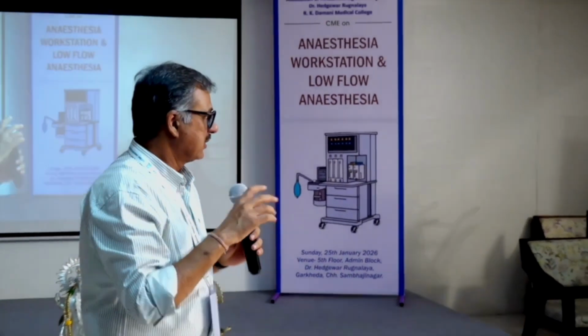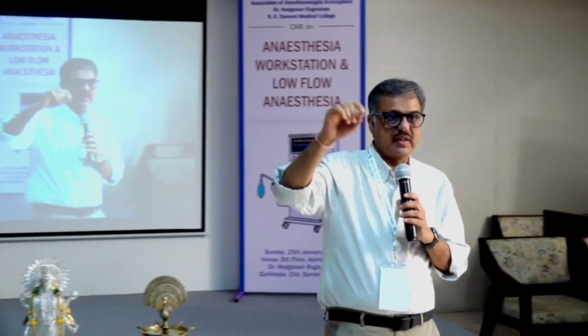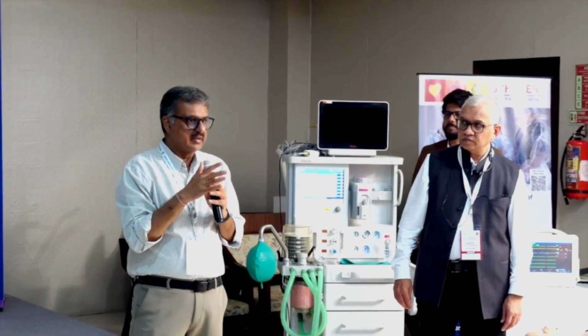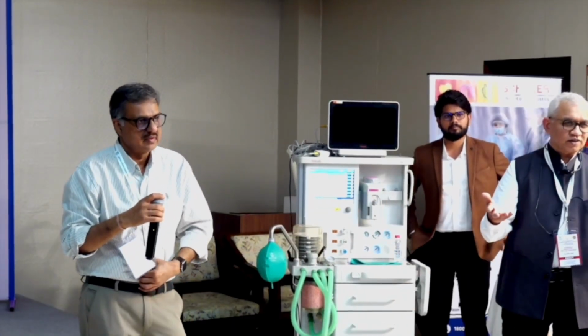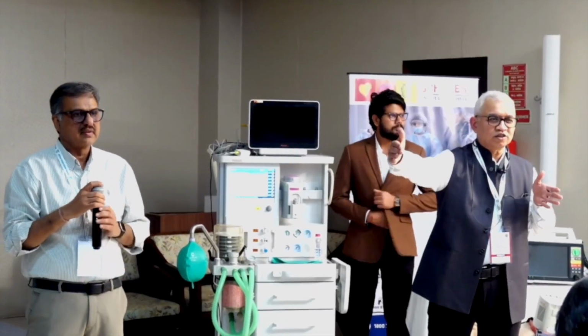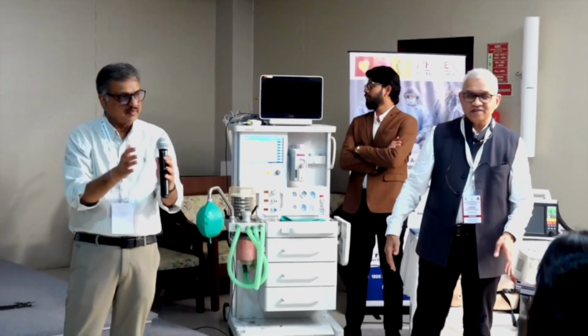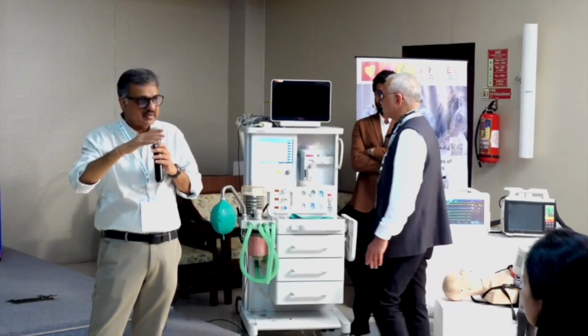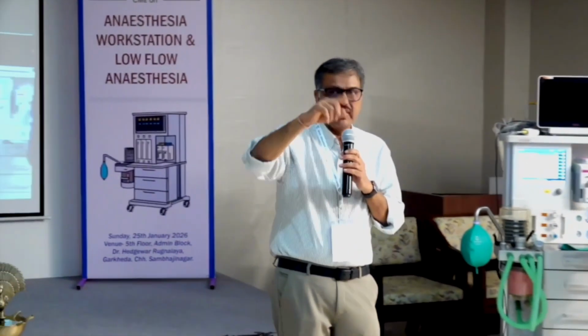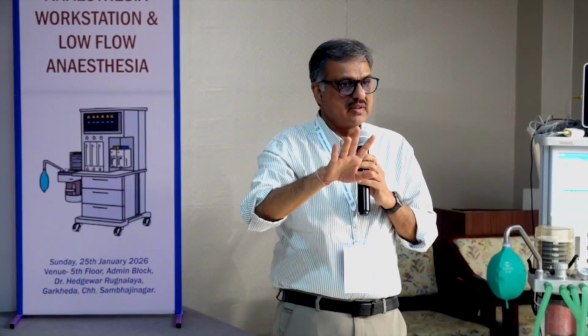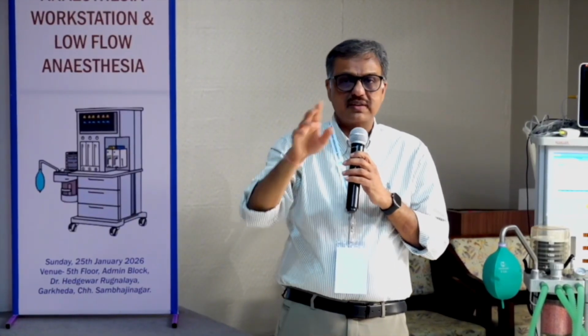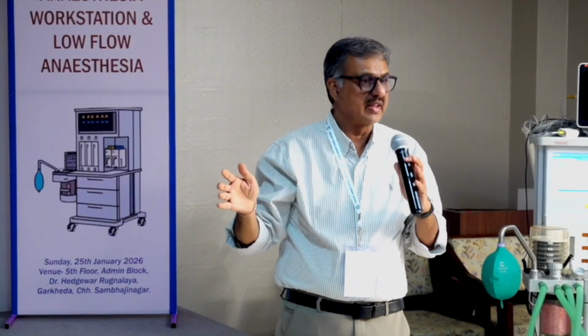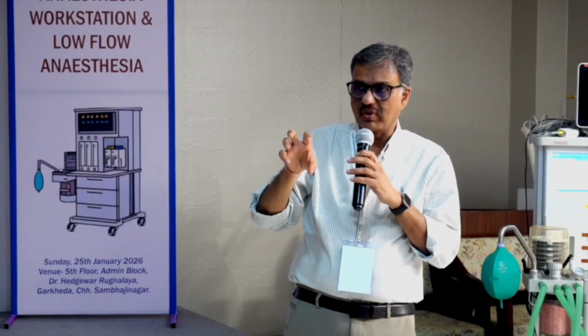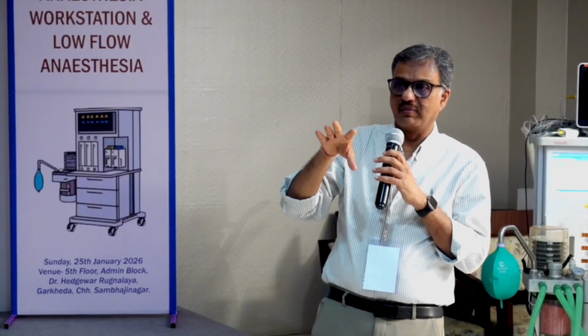What is the clinical significance of that compliance? 6 ml per centimeter of H2O. So with each centimeter rise, at 10 peak pressure, 60 ml is lost in the system, in the circuit expansion. So if your airway pressure exceeds 20, then 20 into 6 means 120 ml is getting wasted in the circuit expansion. So that's the importance of measuring the circuit compliance.